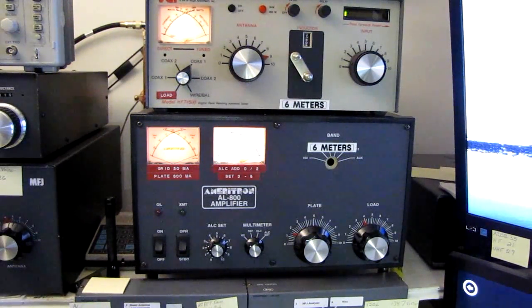When the winter time comes around, the line voltage goes up to a solid 120. In the summer it's down around 115, which is a huge improvement, because before I had them put the new transformer in, it used to be 107 on a very good day and get down to about 90 volts in the summertime. It used to be miserable here.